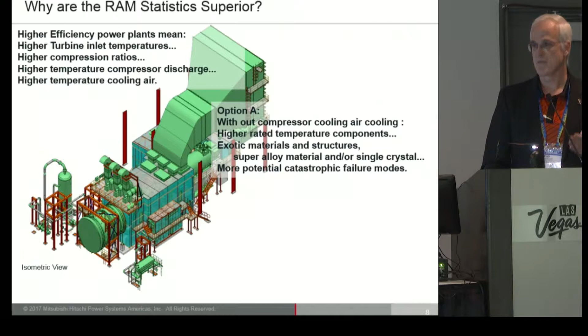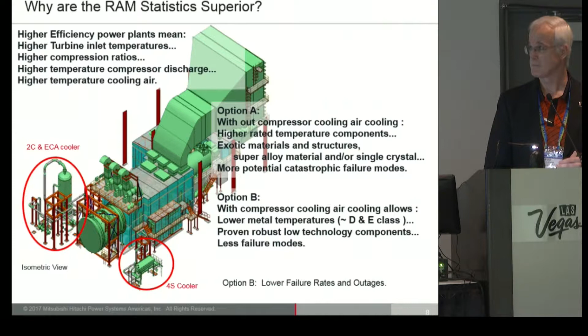Or we do option B. We use coolers. We cool the compressor discharge air down to a more reasonable temperature and use it for cooling. We use less cooling air, so we can get more efficiency that way. But also the metal temperatures are down, and with the same D and E class machine components that we've used and have lots of experience with, the machine is a bit more robust overall in operation and longer lasting. So there are a few less failure modes with the older technology, lower temperature materials.